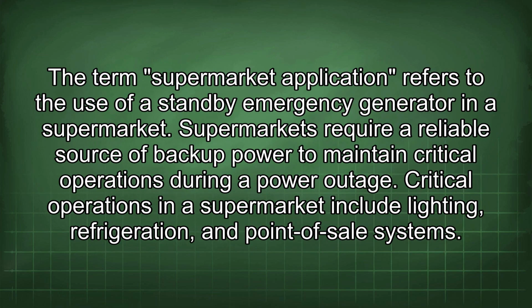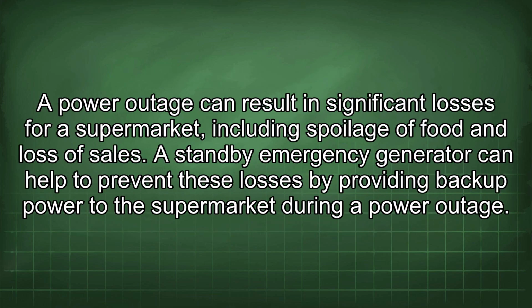The term supermarket application refers to the use of a standby emergency generator in a supermarket. Supermarkets require a reliable source of backup power to maintain critical operations during a power outage. Critical operations in a supermarket include lighting, refrigeration, and point-of-sale systems. A power outage can result in significant losses for a supermarket, including spoilage of food and loss of sales. A standby emergency generator can help to prevent these losses by providing backup power to the supermarket during a power outage.